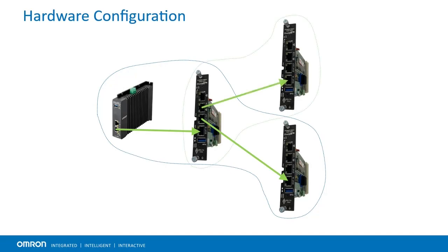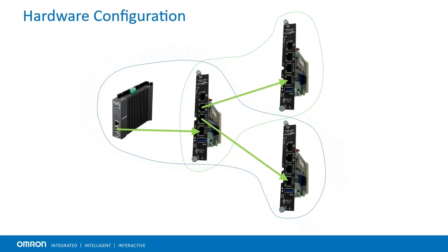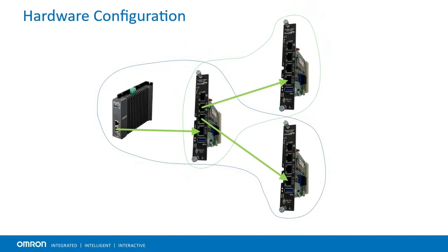This will create a new EtherCAT network — one with your original Master device and the 1040 as an EtherCAT Slave, and one with your 1040 CPU as the Master. In this way, the 1040 CPU can even function somewhat like an EtherCAT Bridge, as long as you manually pass the data the 1040 receives from its own slaves to your other master.